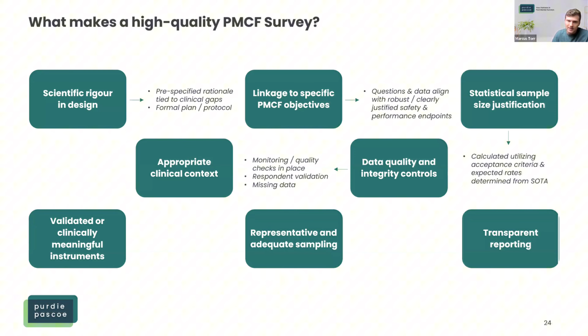Make sure questions have appropriate clinical context. Level 4 surveys can be based upon patient charts or records. It's an area as well where you need to make sure you're following any local regulations. Does it need EC approval? Does it need IRB approval? Can you avoid it by not collecting any patient identifiable information? But also, if you are trying to do a level 4 survey where you need respondents to go back and look at specific information on these cases, is it even possible for that device? Are they recorded, or are you still relying on recollection? On those with physicians completing these surveys, which again potentially risks that survey being defined as a level 4 survey.